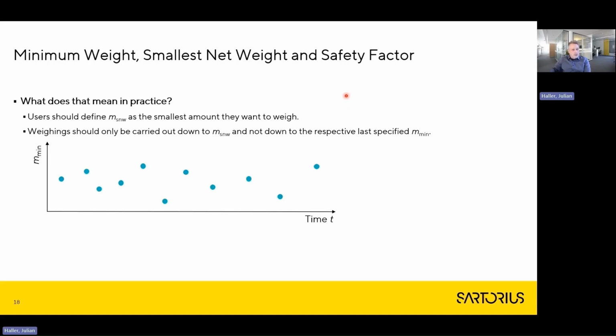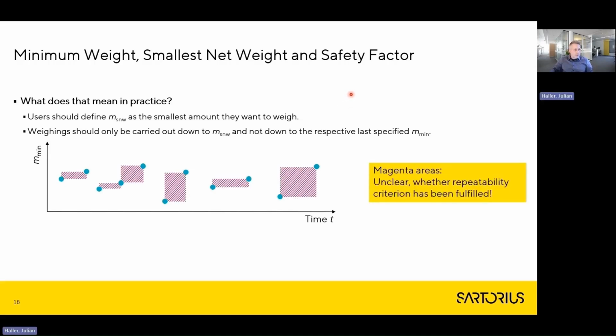If users now weigh down to the last minimum weight that has been determined, for example, in this case, down to this value, and the next minimum weight determination then yields a higher value, it cannot be excluded that in the time between, all weighings between these two values did not fulfill the repeatability criterion. Therefore, the better strategy is to define the smallest net weight for that balance, keep it constant, and consider the minimum weight determinations just as confirmations that the smallest net weight still is bigger than all determined minimum weight values.